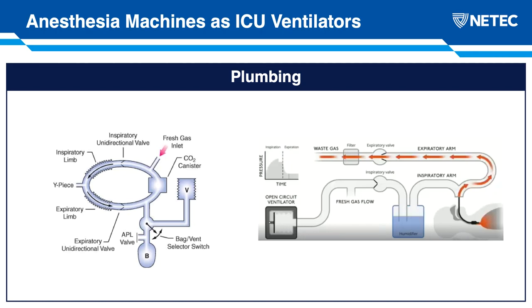An anesthesia machine, on the other hand, is really best studied by the slide over here on the left. What we can see on the left with the anesthesia machine is that they have something called a circle system. And in this slide, I guess it's best depicted as an oval more than a circle. But what you can see here is that air and oxygen is pressurized, either via a bellows through a ventilator or through a bag. And whether you're pressurizing via the bellows or via the bag is selected by a switch. And then that is pressurizing the circuit. And fresh gas comes in, it makes its way through the inspiratory valve and on into the patient's lungs through this Y piece here. And on the way back, it goes through the expiratory limb.